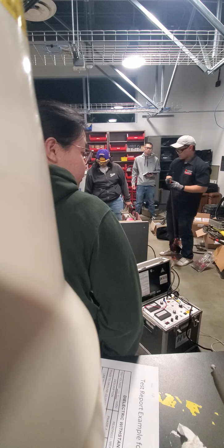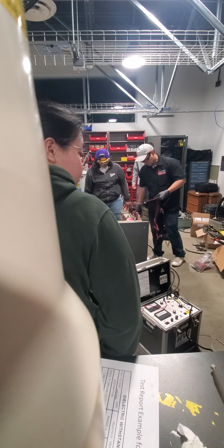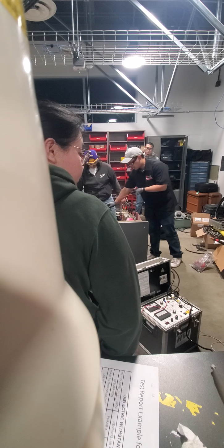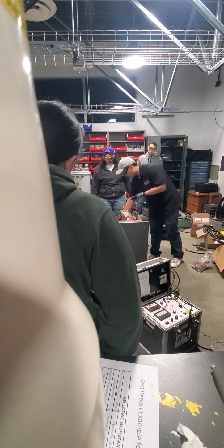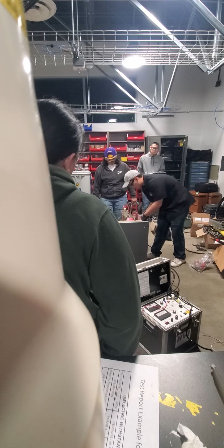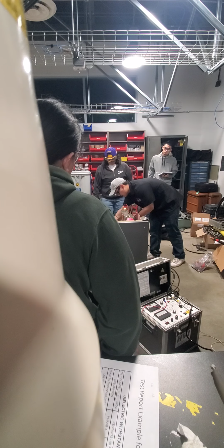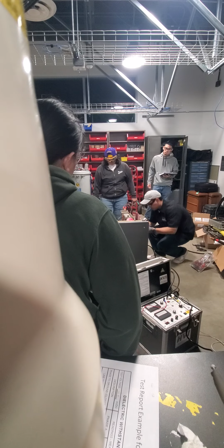Right, so we're going to ground all of the phases that are not under test, for safety - anything that is not a phase. And because it's line to load, we're also going to want to do that on the line side and load side.